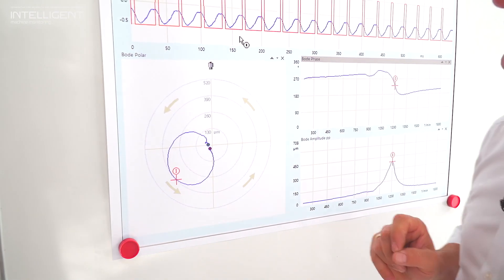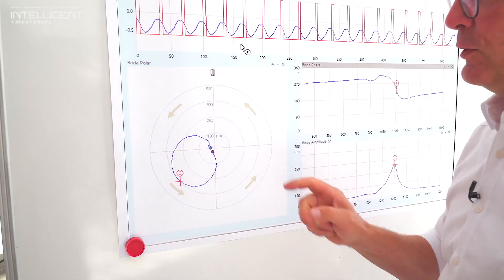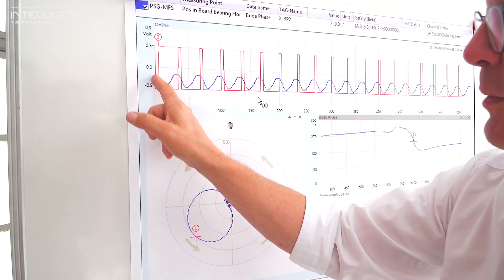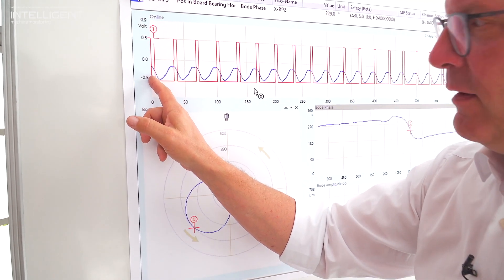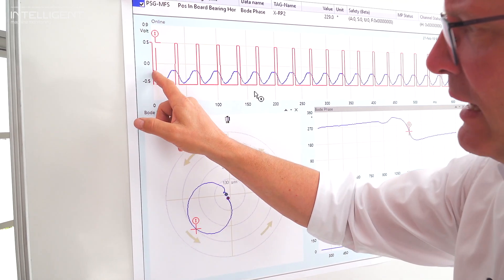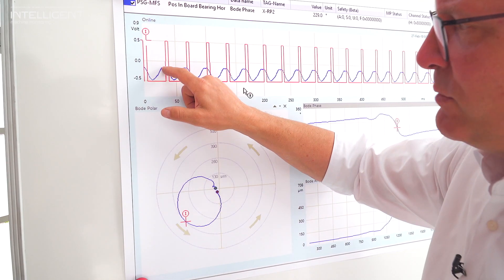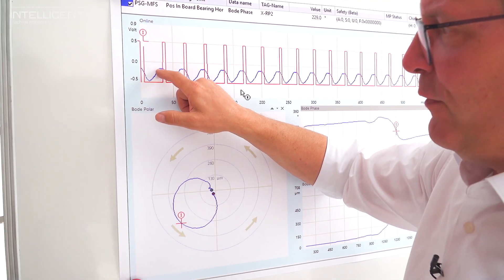What we also need is a key phaser to get the speed information. Here we see the information from the key phaser when the rotor passes the key phaser. Then we see from the starting point from the key phaser to the maximum amplitude, we see the phase.